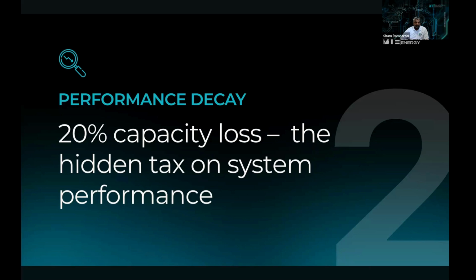Right now we need to meet nameplate capacity all the time, especially on our PPAs, but there could be up to a 20% capacity loss. That loss comes from how the system is balanced and the environment due to heat. Even though everyone says liquid cooling is a great technology, and we use it in our systems too, while the pack itself is being cooled during operation, the environment around where the container is sitting is also a major contributor to heat loss, which is one of the biggest problems causing decay to happen much faster.